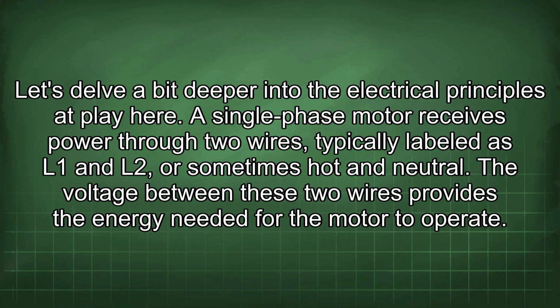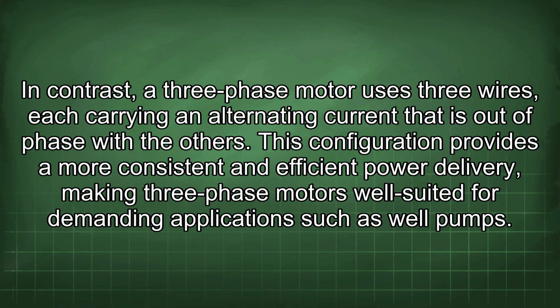A single-phase motor receives power through two wires, typically labeled as L1 and L2, or sometimes hot and neutral. The voltage between these two wires provides the energy needed for the motor to operate. In contrast, a three-phase motor uses three wires, each carrying an alternating current that is out of phase with the others. This configuration provides a more consistent and efficient power delivery, making three-phase motors well suited for demanding applications such as well pumps.